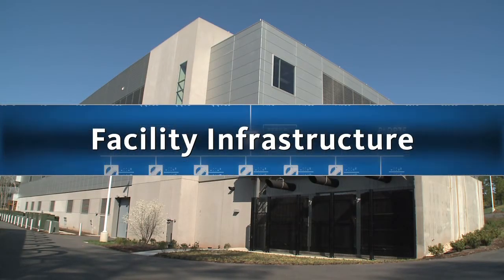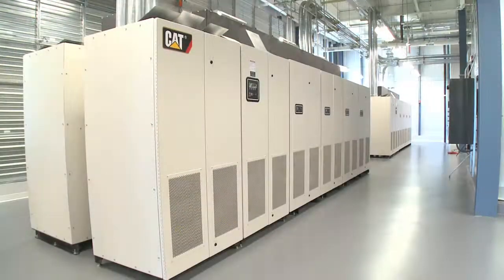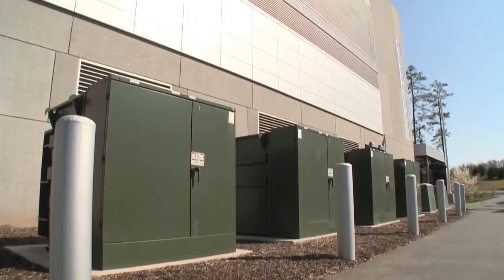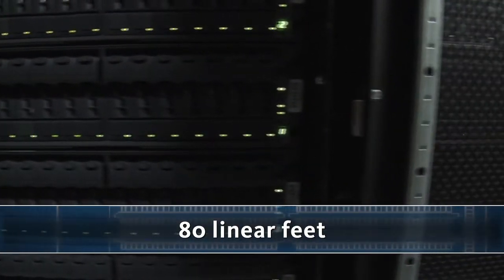This building is basically a three-story structure. The primary power is fed by utility transformers on the other side of the wall, which then comes into the secondary transformers and then fed directly upstairs to the UPS, and from there fanned out to the data center floor. This means the distance between the utility power and the load is as little as 80 linear feet.